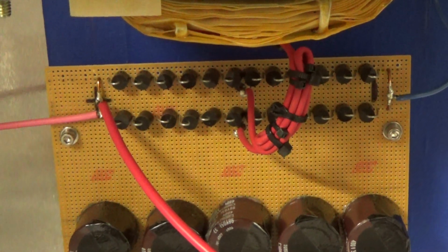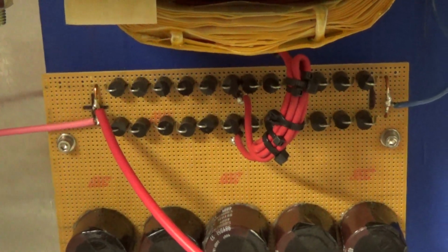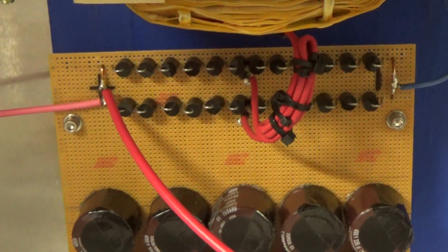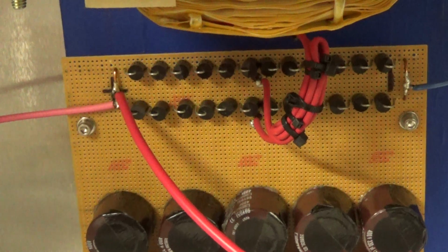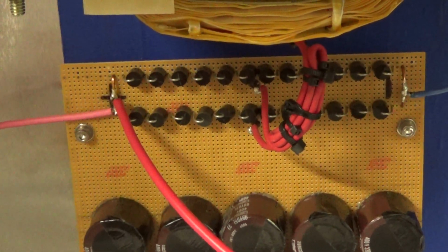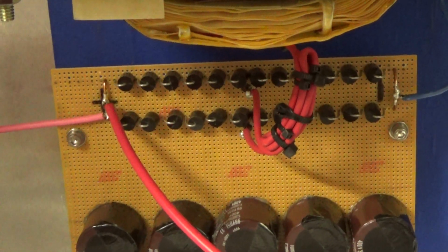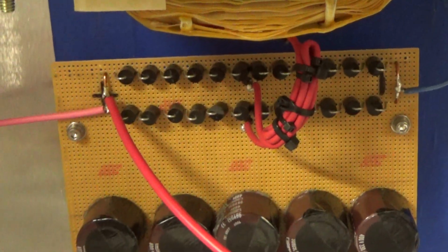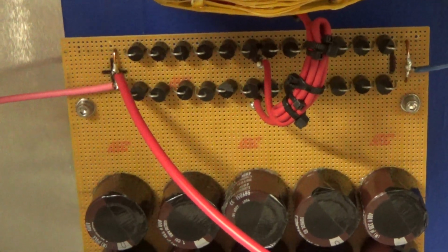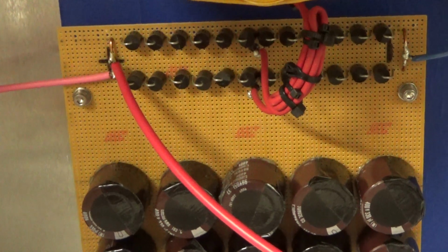So you take 2650, which is the secondary AC voltage rating, and divide that by 240, come up with 11.04 volts. So take 11.04, multiply it by whatever you're feeding into it above that rating on the transformer, let's say 248.